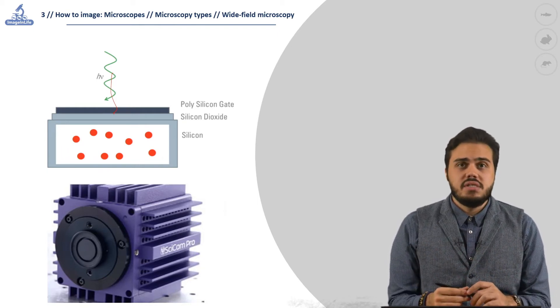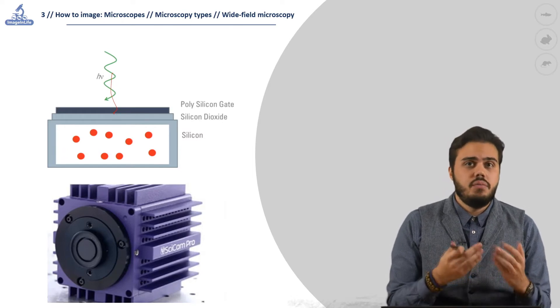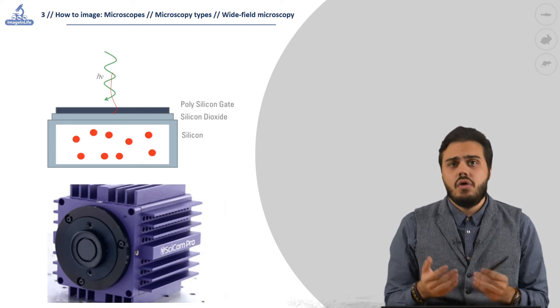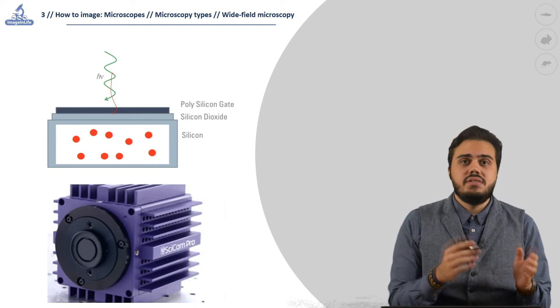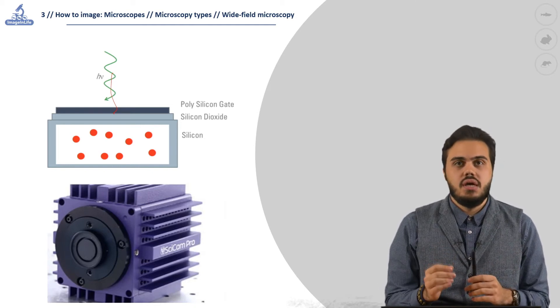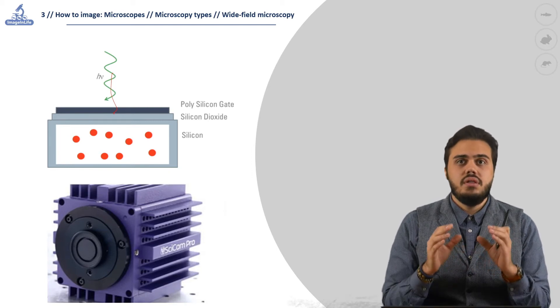The CCD cameras have a better signal-to-noise ratio, where the CMOS has a higher frame rate. EMCCD and sCMOS are the scientific evolution of normal cameras. The sCMOS have a poorer quality but can go up to 1000 fps, while the EMCCD are able to capture really dim signals.